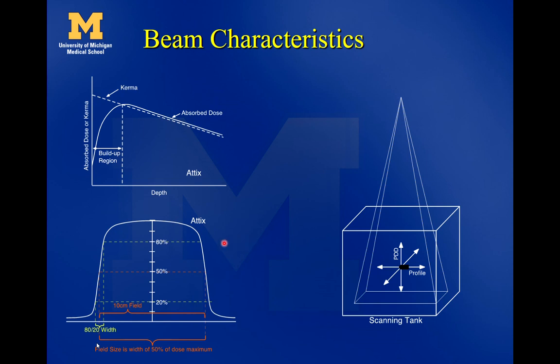We normalize these profiles to 100% at some preferred depth — maybe Dmax or 10 cm deep. We tell the software that the central axis value should be 100%, and it rescales the graph accordingly.